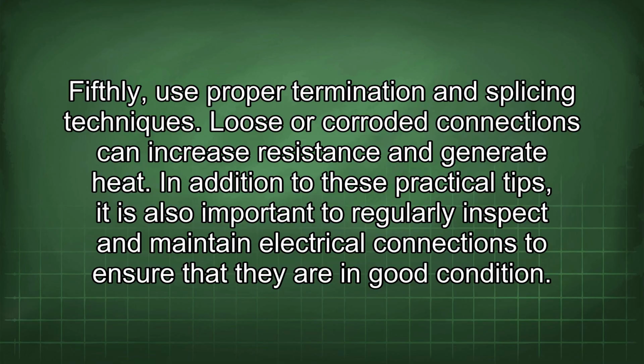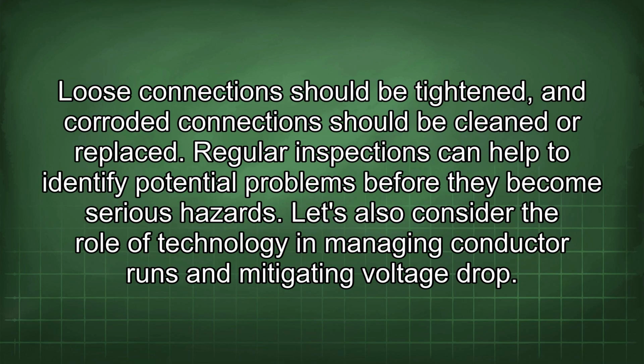In addition to these practical tips, it is also important to regularly inspect and maintain electrical connections to ensure that they are in good condition. Loose connections should be tightened, and corroded connections should be cleaned or replaced. Regular inspections can help to identify potential problems before they become serious hazards.